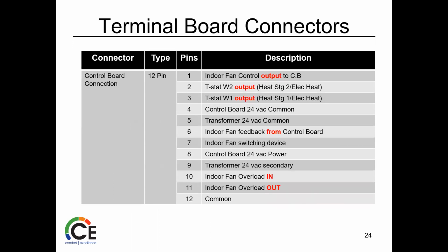12-pin control board connection. Again, now you've got your W2, your W1, indoor fan controls. It's where your transformer ties in to power everything. Indoor fan overload in and out. So all of them have a fan overload. Some of them used to be a smaller switch. If we talk vane axial, we've got that stator limit, but that's where that ties in. So again, when we're talking the path, these are a couple things that we're checking. All right, do you have power here or not? And this is why we're doing that.